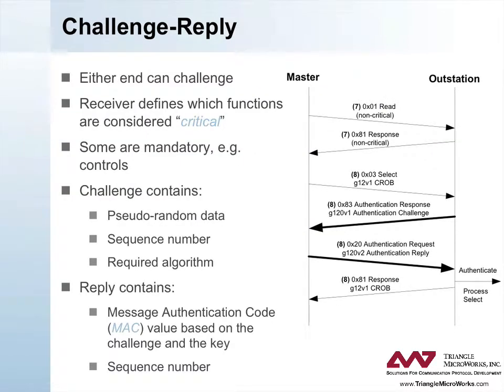DNP3 secure authentication is by default based on a challenge-reply mechanism. Either the master or the outstation can challenge any normal DNP3 message it receives. The receiver of the message can determine that any DNP3 function is critical, requiring authentication. However, the specification does specify that certain functions must be considered critical, such as control operations: select, operate, direct operate, etc.